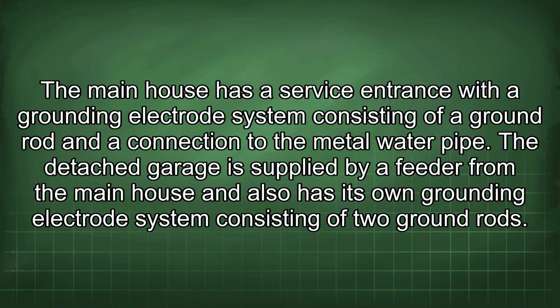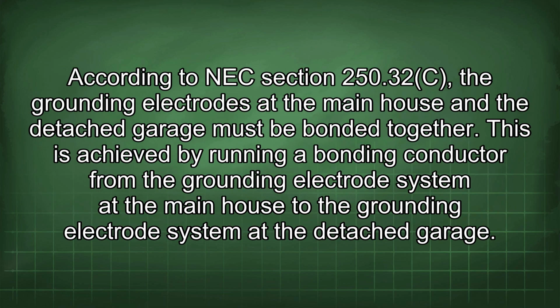The detached garage is supplied by a feeder from the main house and also has its own grounding electrode system consisting of 2 ground rods. According to NEC Section 250.32(C), the grounding electrodes at the main house and the detached garage must be bonded together. This is achieved by running a bonding conductor from the grounding electrode system at the main house to the grounding electrode system at the detached garage.